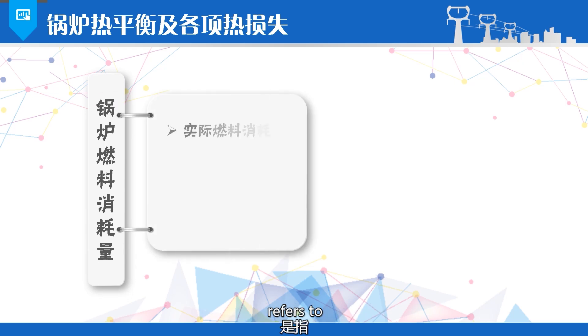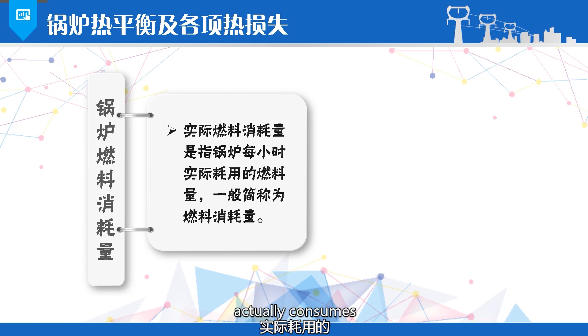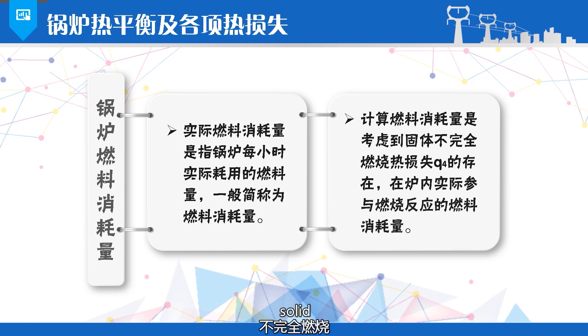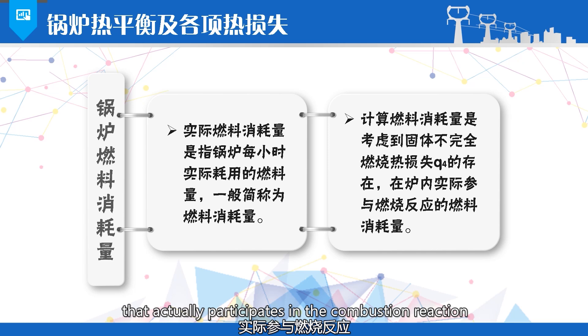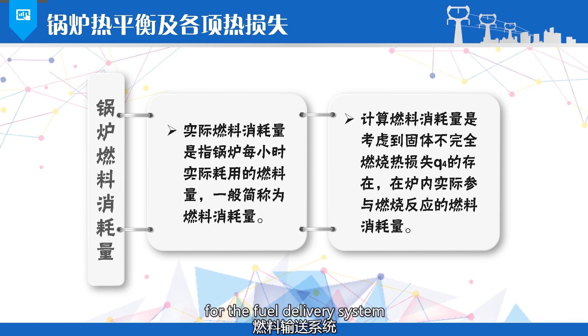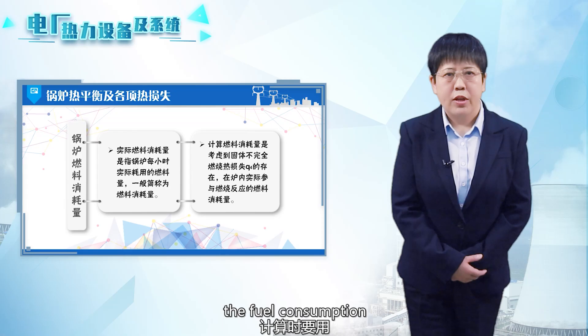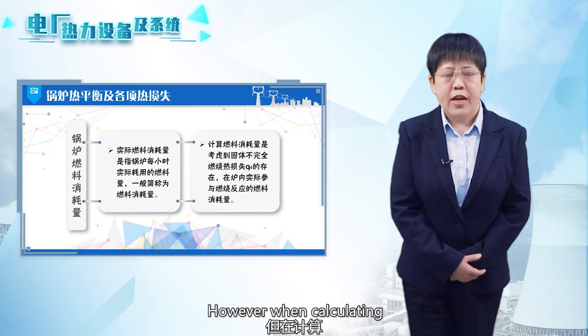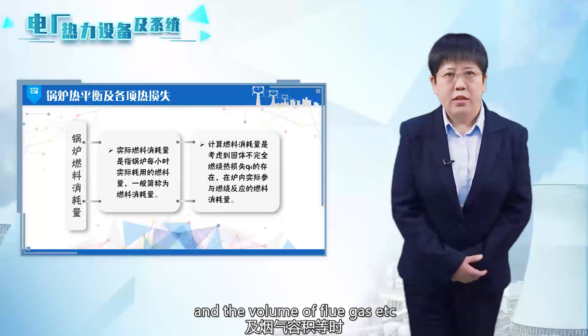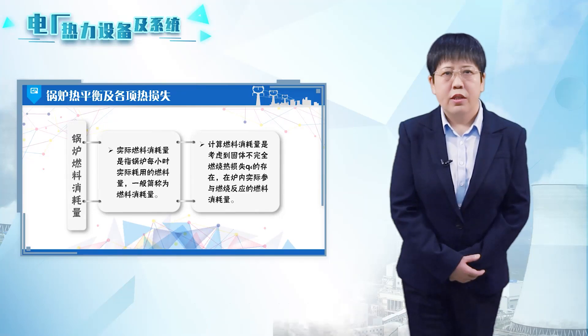The actual fuel consumption refers to the amount of fuel that the boiler actually consumes per hour, often simply referred to as the fuel consumption. The calculated fuel consumption takes into account the existence of solid incomplete combustion heat loss — it represents the amount of fuel that actually participates in the combustion reaction inside the furnace. These two types of fuel consumption serve different purposes. When conducting calculations for the fuel delivery system and the pulverizing system, the actual fuel consumption is used. However, when calculating the amount of air required and the volume of flue gas, it is necessary to use the calculated fuel consumption.